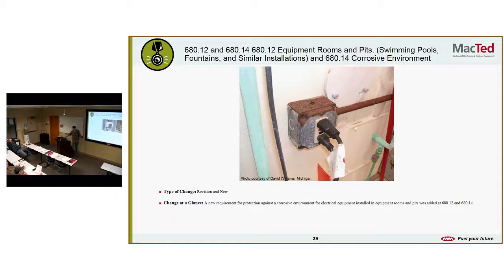Equipment rooms and pits, swimming pools, fountains, and similar installations. We have a revision and a new requirement. A new requirement for protection against corrosive environments for electrical equipment installed in equipment rooms and pits was added at 680.12 and 680.14. I'm going to guess that requirement has something to do with corrosion protection, maybe stainless steel, something like that. Or plastic.